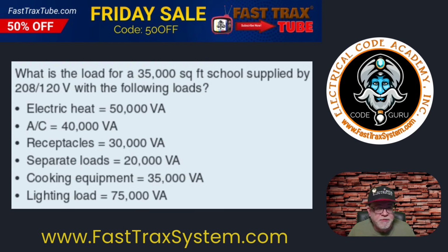Now, in this case, it's a 3-phase 208-120. So the square root of 3 is 1.732, right? So we take the 208 times 1.732. That gives us, hold on here, 208 times 1.732. That gives me 360.256. It's not going to change whether you just want to use 360. If you want to round it to 360.26, it's not going to make a difference. We'll use the exact value, 360.256.